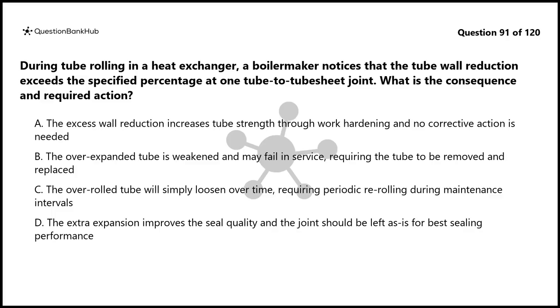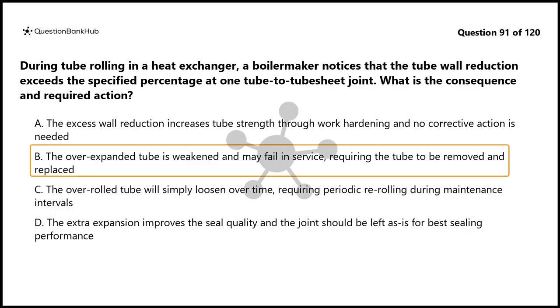The correct answer is B. When tube wall reduction exceeds the specified percentage during rolling, the tube has been overexpanded. Overrolling thins the tube wall beyond the design limit, weakening the tube and reducing its ability to withstand internal pressure and thermal cycling. The tube material may also develop microcracks from excessive cold working. An overrolled tube can fail in service, causing a leak between the tube side and shell side fluids, which may create safety hazards and equipment damage.